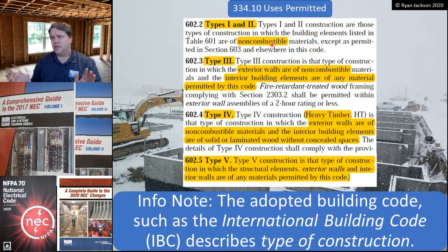Every wall in the building, like if you're in a high-rise building, we don't let you build wood walls in a 50-story building. It just ain't gonna happen. Even if they're not structural, we can't have that much fire fuel in a 50-story building. So types 1 and 2 are completely non-combustible. Here's the way you can look at it. For other than dwellings, for commercial, if the building has to be non-combustible by the building code, then so does the wiring method. NM cable is combustible. We limit how much combustible stuff you can have in a non-combustible building.